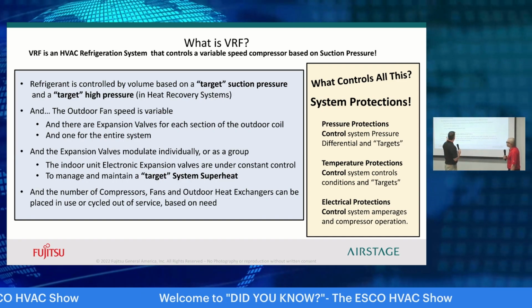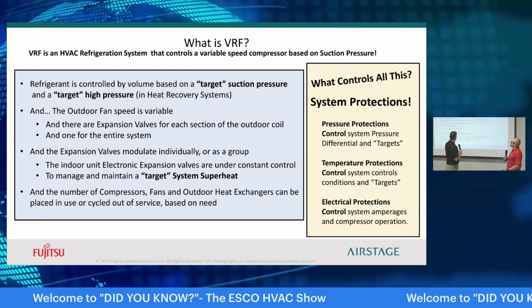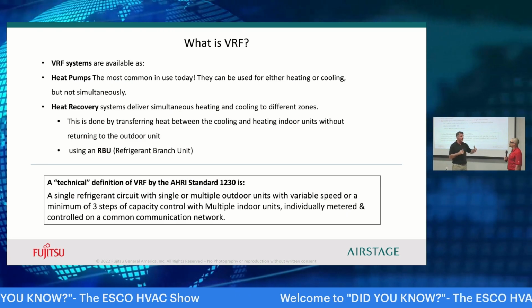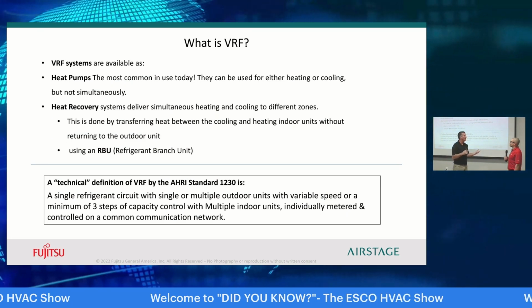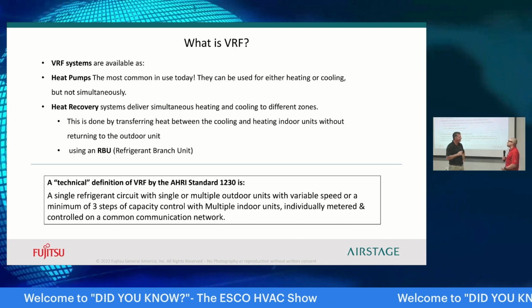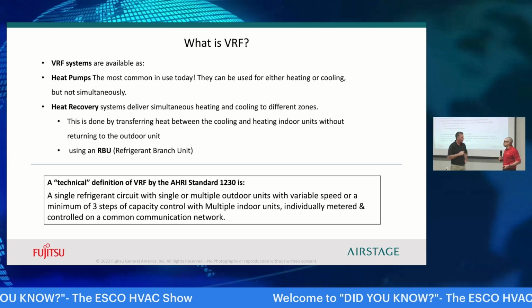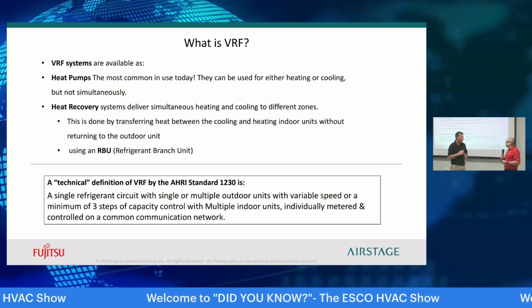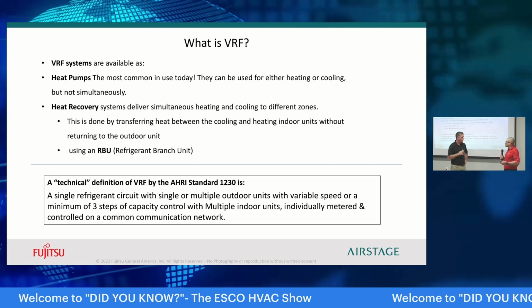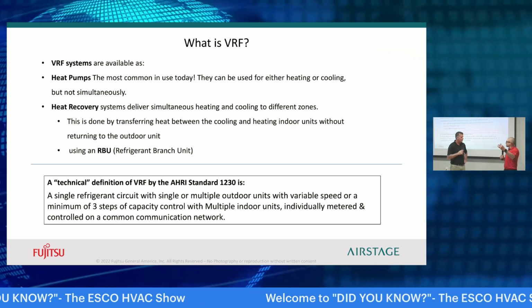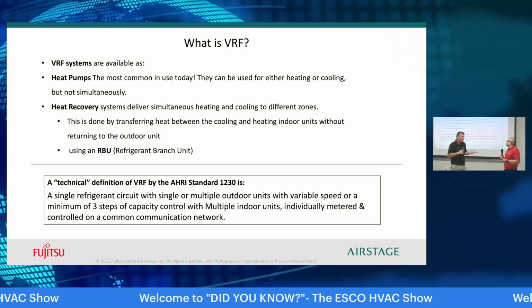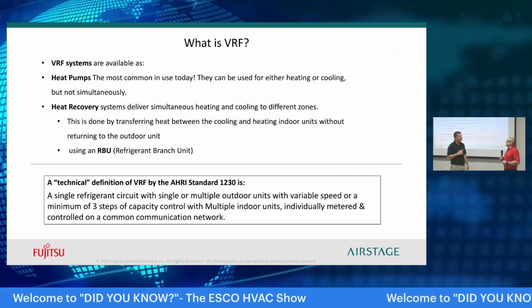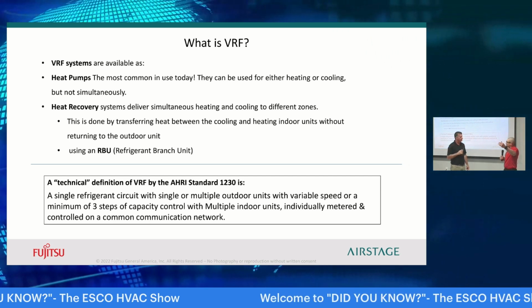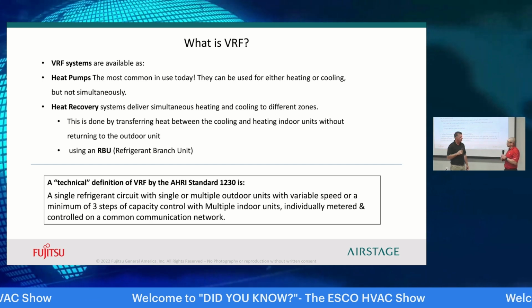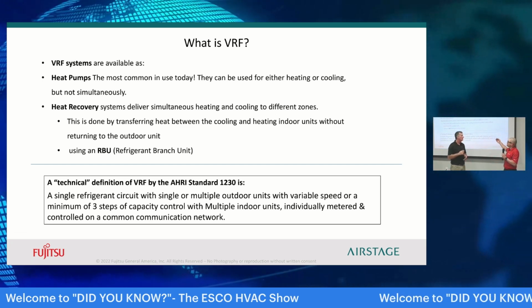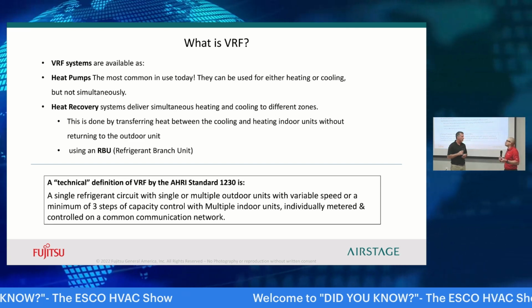So if we talk about what VRF is, and look at some of the differences, we may add things like a branch controller, an RBU. Heat recovery, having the ability to do heating and cooling simultaneously, requires an RBU, a refrigerant branch unit that goes between the outdoor unit and the indoor units. It's just an additional component to capture that thermal energy that would otherwise be displaced. We grab that thermal energy with the RBU and send it to a unit that's in need, so we're not wasting energy per se.